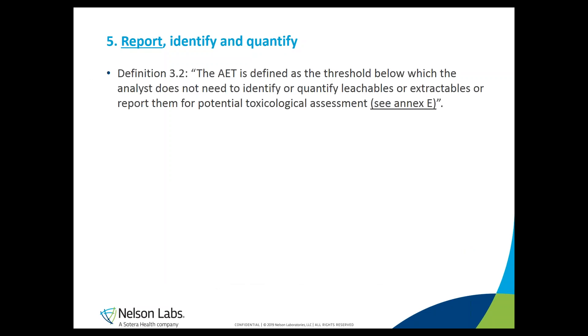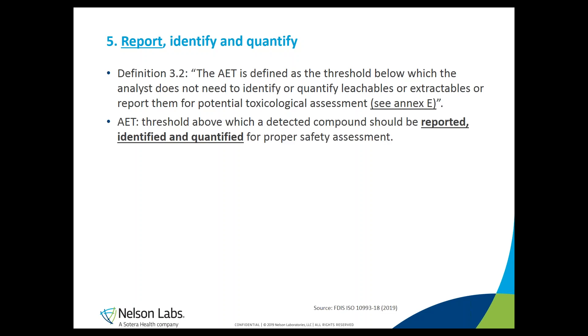There is a clear definition of the AET in this new final draft. It is defined as the threshold below which the analyst does not need to identify, quantify, or report leachables or extractables for potential toxicological assessments — see Annex E. In other words, it is a threshold above which a detected compound should be reported, identified, and quantified for proper safety assessment. But how do you exactly determine it? Is there a specific guideline?